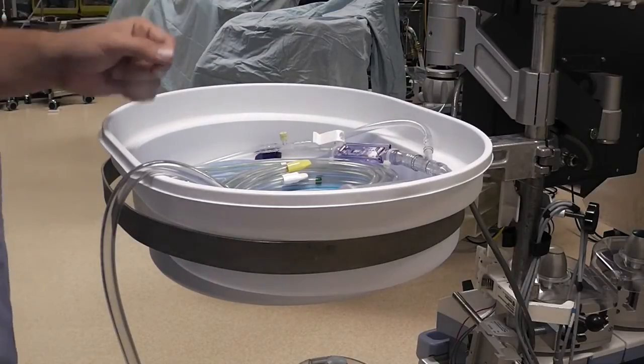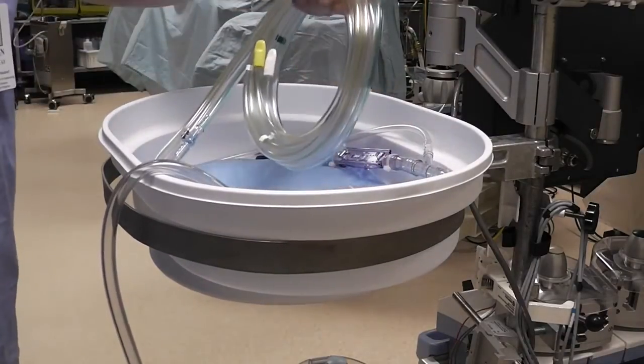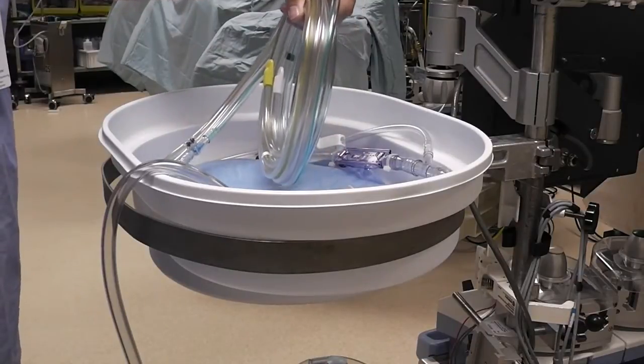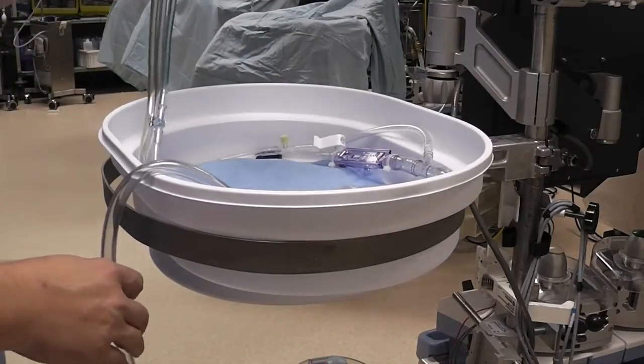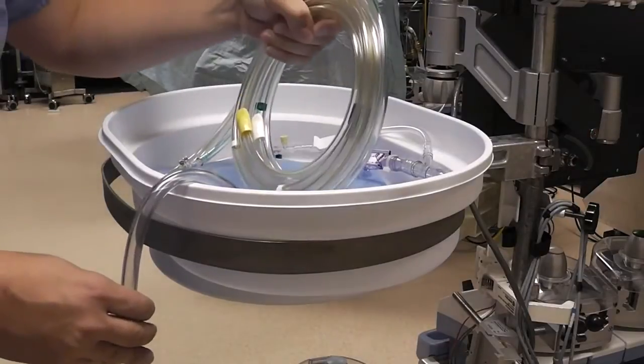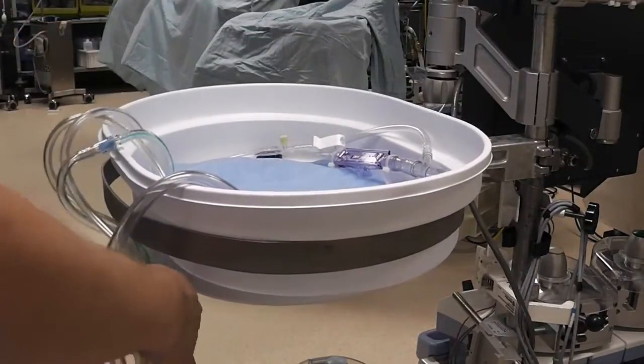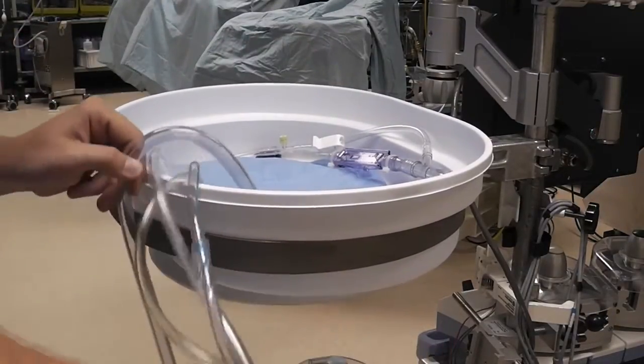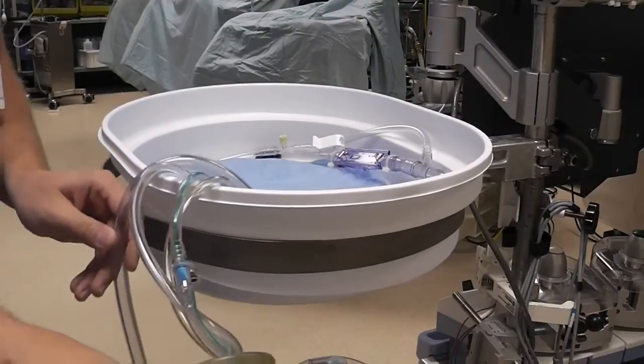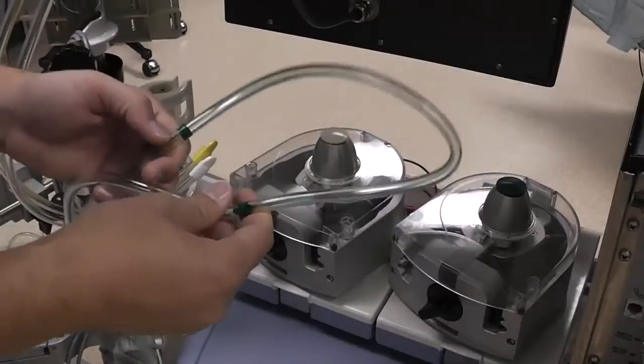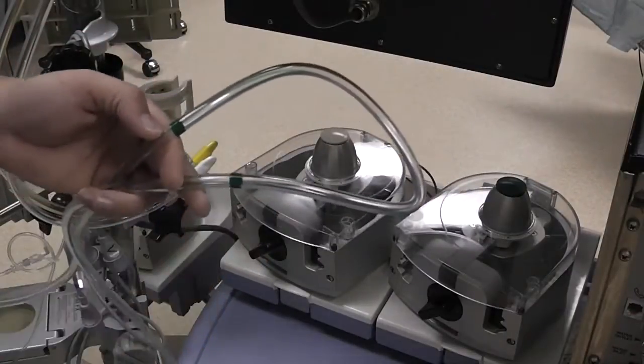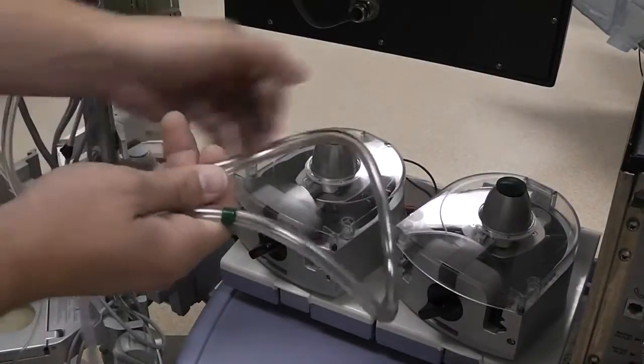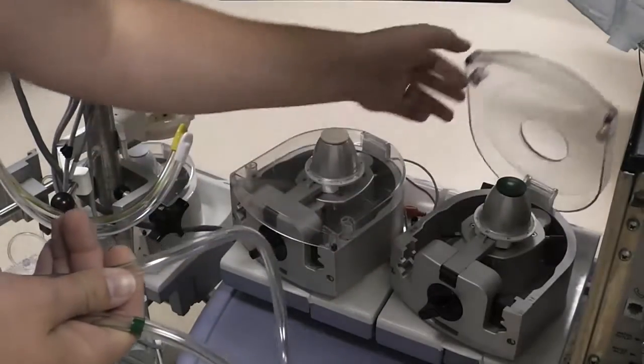Okay, next we're going to take the lines for the vent and the suckers and put those into their pump heads. So in the pack here, grab the coil of lines, and you want to then take these and roll them underneath the arterial line so that they sit correctly when they go up to the table. Okay, now we're going to take the green line, which is the vent line, and put it in the pump head.